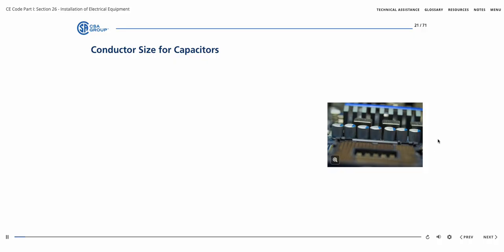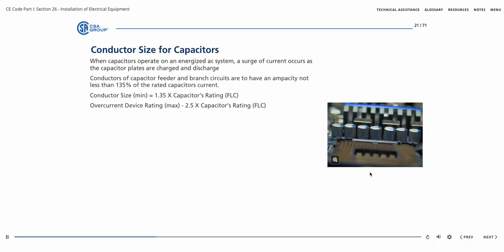This portion of Section 26 includes Rules 208 through 268 and focuses on capacitors and transformers. Beginning with Rule 26-208, it is required that when capacitors operate on an energized AC system, a surge of current occurs as the capacitor plates are charged and discharged. Since the polarity of the capacitor plates changes every half cycle, there is a small continuous surge on the capacitor's supply conductors if the capacitor is energized. Sub-Rule 1 requires that conductors of capacitor feeder and branch circuits are to have an ampacity not less than 135% of the rated capacitor's current.